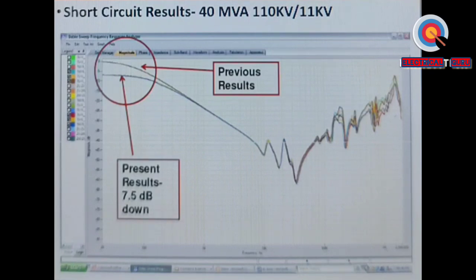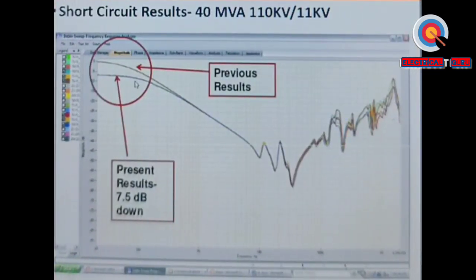So the DC test on the transformer should be done last, because if you do a DC test in the beginning, there are chances that some permanent magnetism may remain, that is, residual magnetism in the core because of the DC, and unless demagnetization is done, some of the test results may be erroneous. So after we demagnetized these transformers, this blue line came, which shows what is normal. Earlier it shifted by 7.5 dB, which was an indication that the core has some residual magnetism.